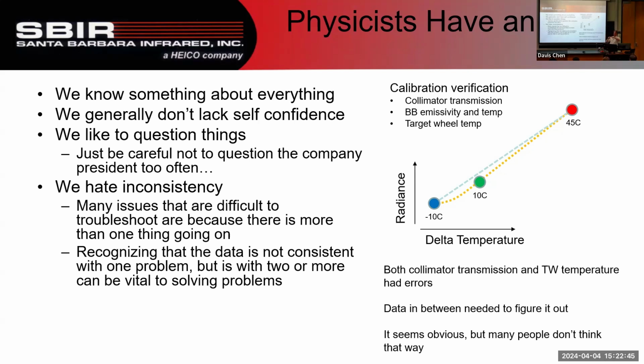Cold air fell down onto the collimator. And the temperature sensor on the target is not sitting on the target, it's inboard of the target. So the cold air would fall down and cool half the target wheel, but not the other half, which is covered up. So you get a gradient across the target wheel. The temperature sensor was measuring the temperature correctly where it was, but that's not actually the temperature of the target. So the slope was wrong, the offset was wrong, which makes two points look right, but they're both wrong. The actual calibration was all wrong.